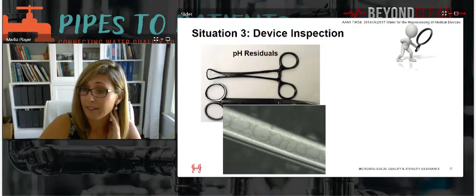Okay, how about this one? Have you ever seen this? This is most commonly observed when devices have a high or a low pH residual following the cleaning and going into steam sterilization. So how about this? White chalky spotting or deposits. Again, this is that hard water being built up. What about this? A case that's lost its color. This typically happens when these types of rigid containers are exposed to chlorinated water, or they're heated with water of high or low pH.